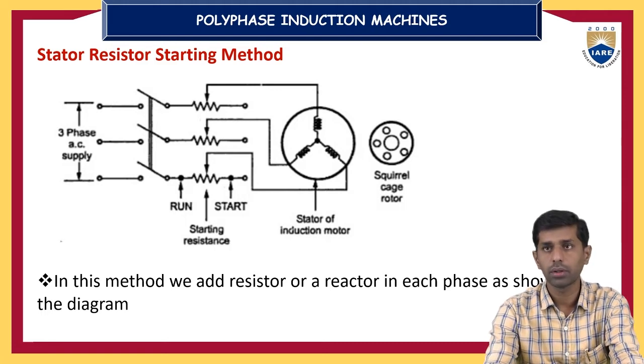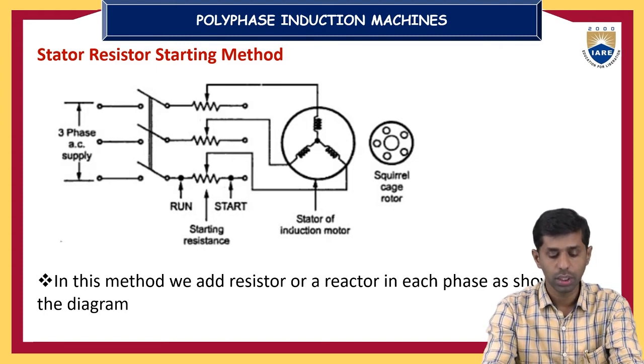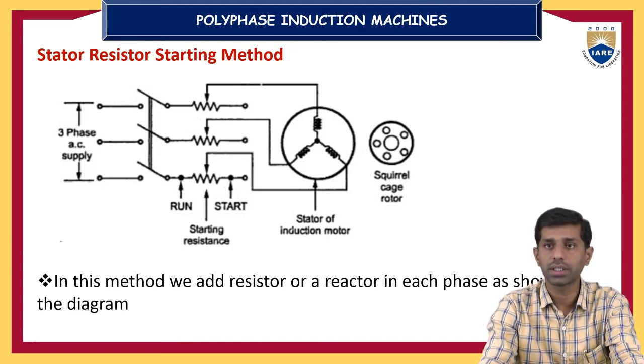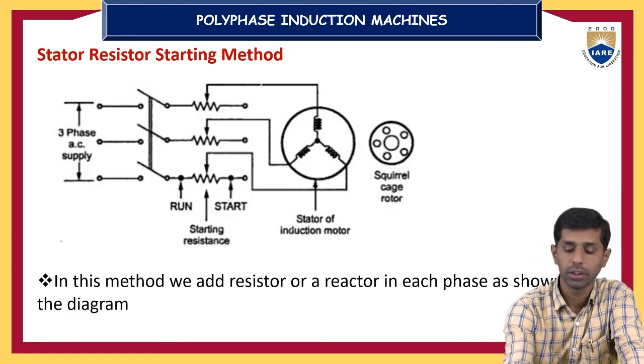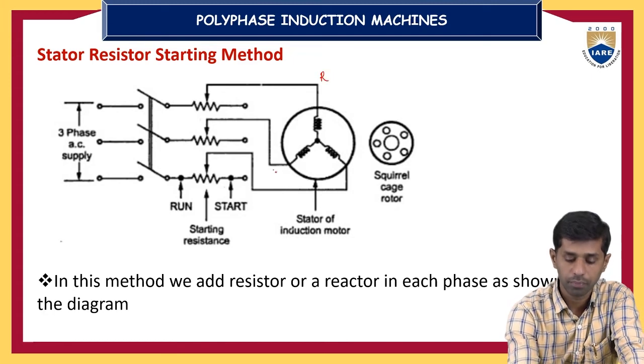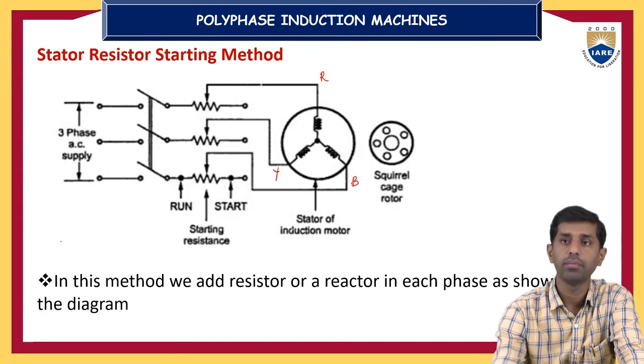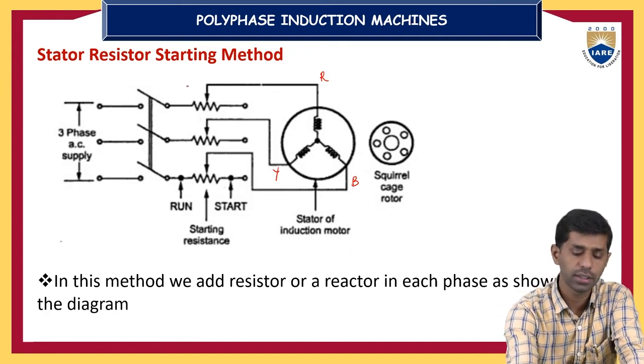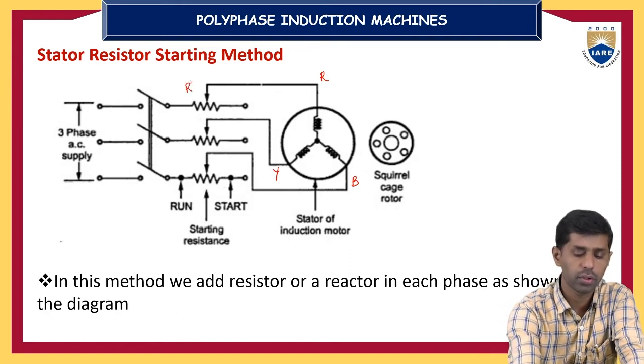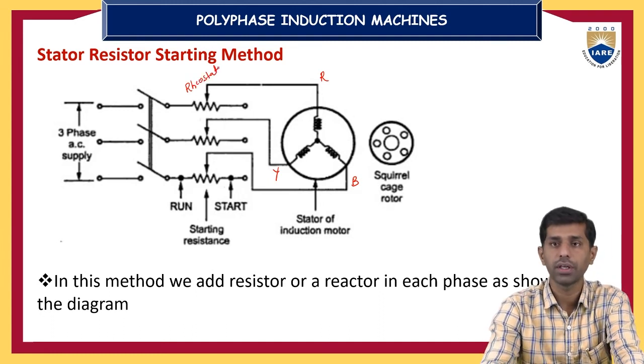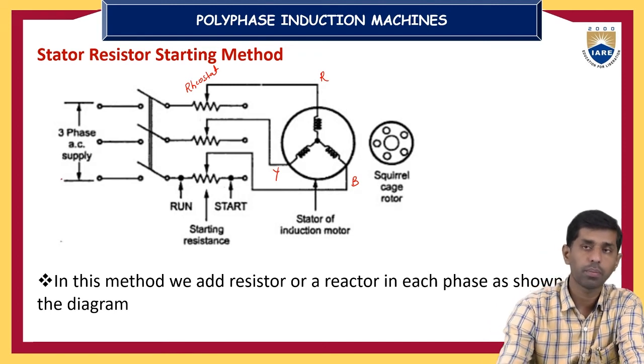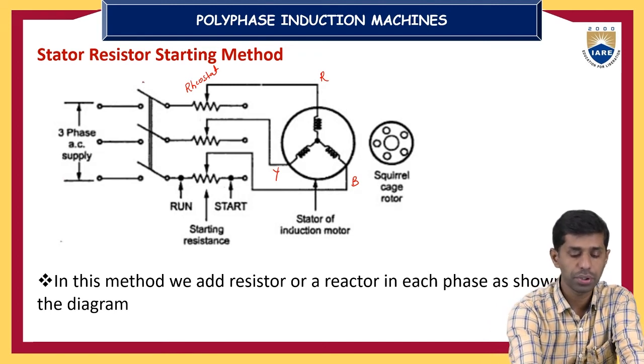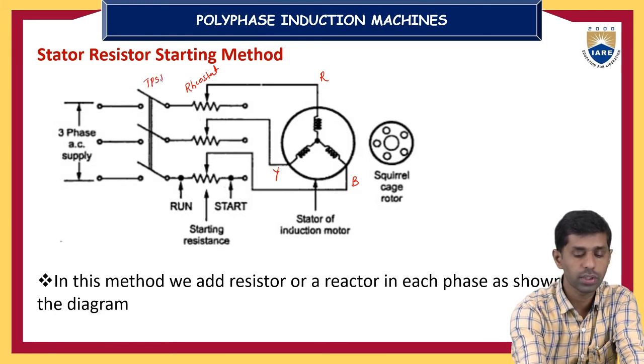It is a very simple method to start the three-phase induction motor and limit the starting current at the time of starting. Simply, we use starting resistors, that is, variable resistors connected to each phase. Let this be the R phase, this the Y phase, and this the B phase. Each resistor is a variable resistor, which we can also call a rheostat. A suitable range of rheostats is connected to each phase. The three-phase AC supply is connected across the TPST switch, a triple pole single throw switch.